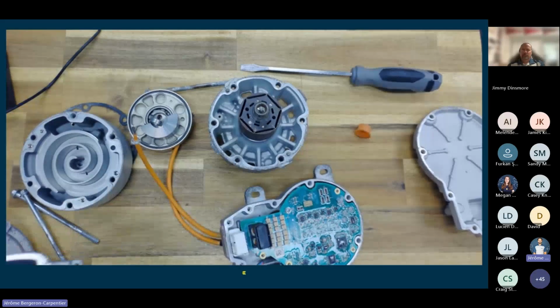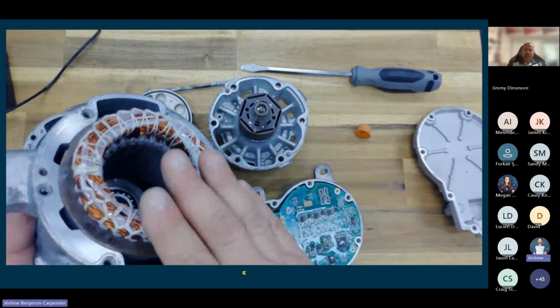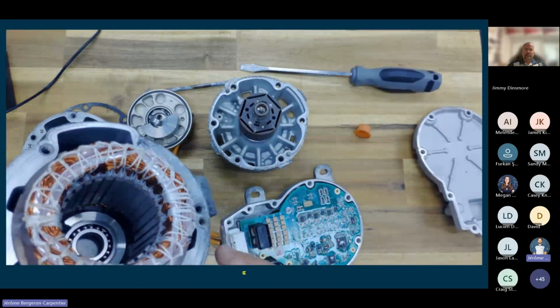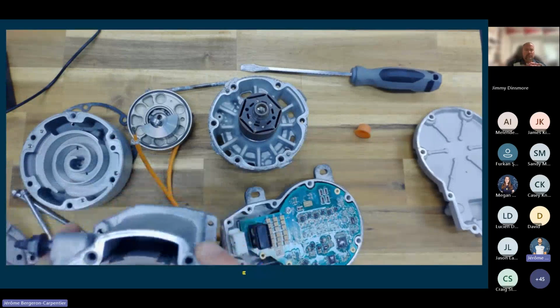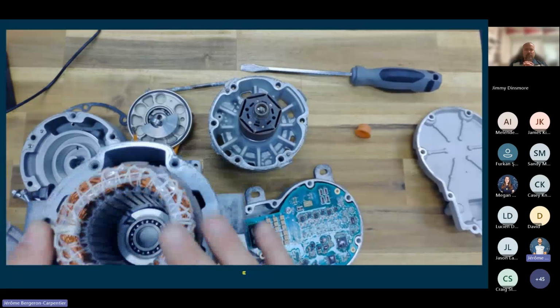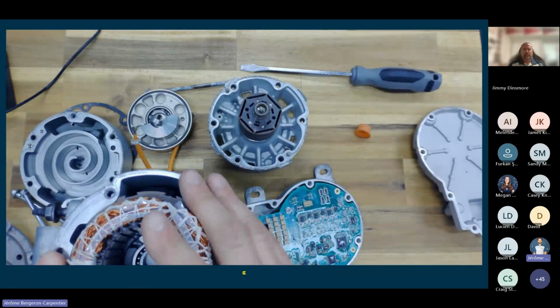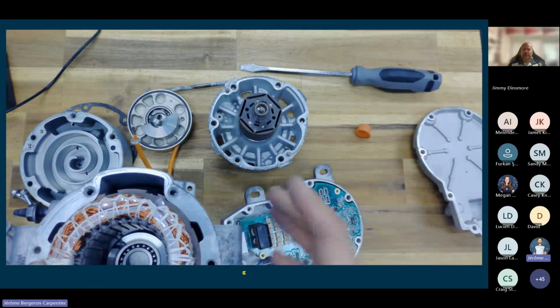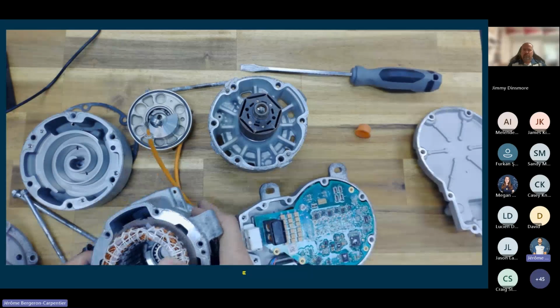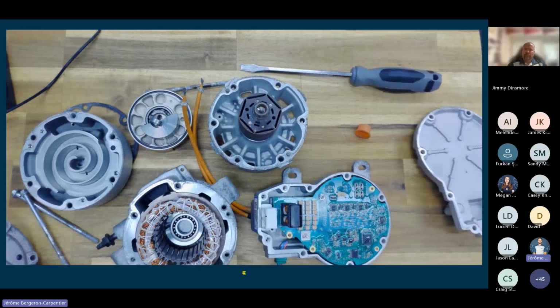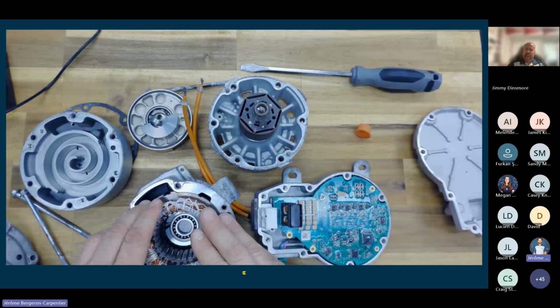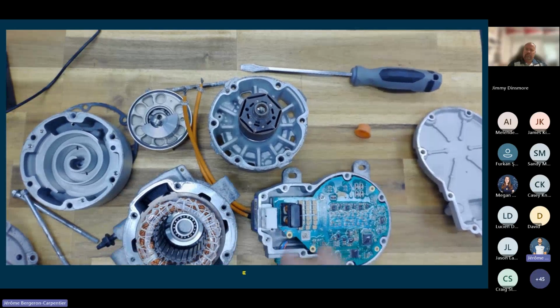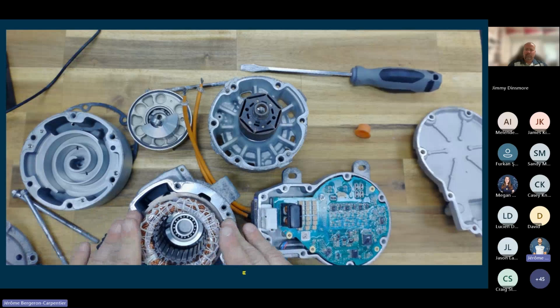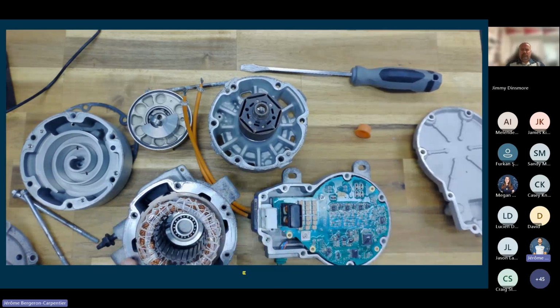And this is one point before I go back to the cars. The oil is critical because you've got to remember the stator and the rotor are exposed to the oil and the refrigerant in the system. If you have the wrong oil, like a PAG oil, and some manufacturers claim that only 1% of PAG oil in the system can cause problems, which can cause isolation loss, which can cause failure, which is a big job if that happens. POE oils, polyester oils, are designed to coat and insulate as well as lubricate the compressor. So it's very important to have the proper type of oil. Always follow manufacturer recommendations. There is no such thing as universal oils in AC systems, whether it's a belt-driven compressor or an electric-driven compressor.